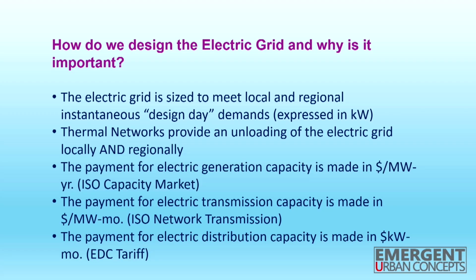Thermal networks provide an unloading of the electric grid locally and regionally. That's pretty darn important. The payment for electric generation capacity at the ISO level, regionally, is made in dollars per megawatt year. The payment for electric transmission capacity is made in dollars per megawatt month on an ISO network transmission basis. The payment for electric distribution capacity is made in dollars per kilowatt month.